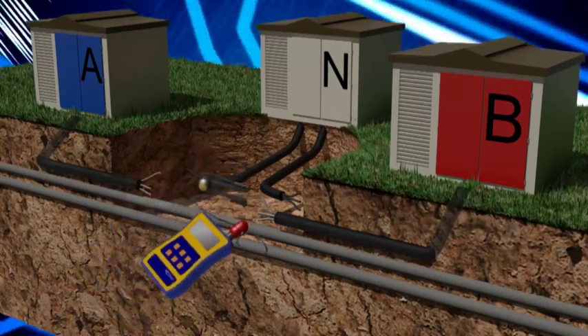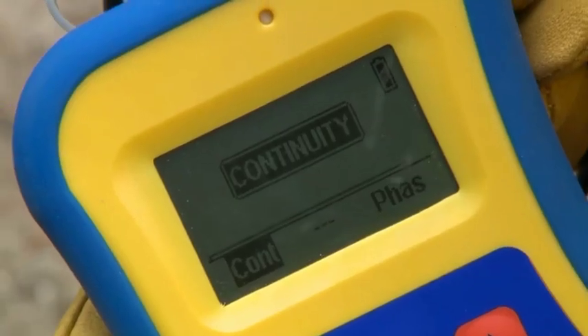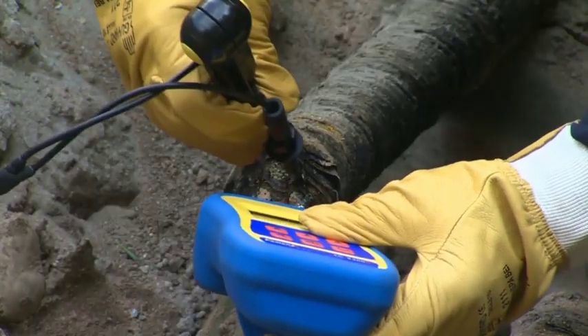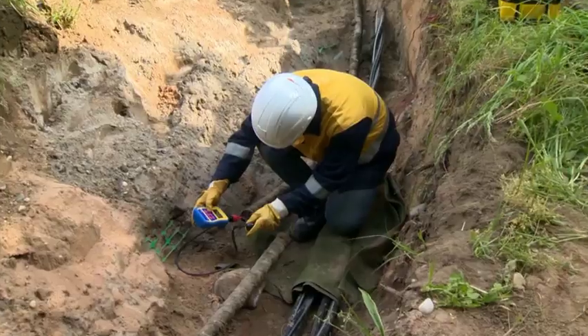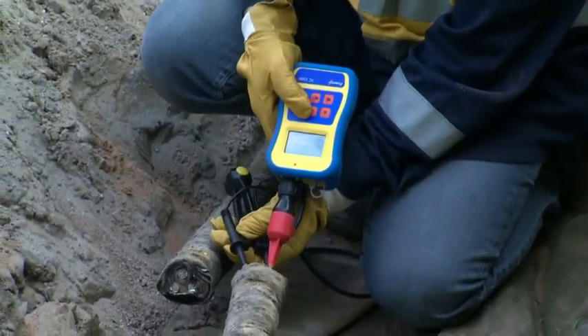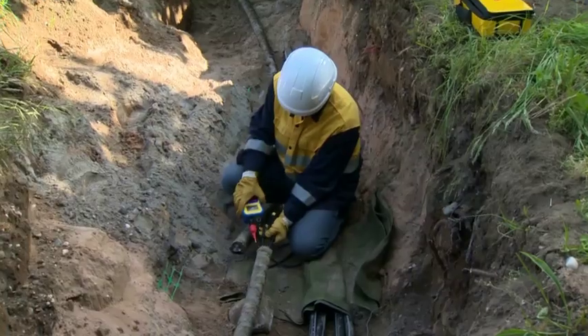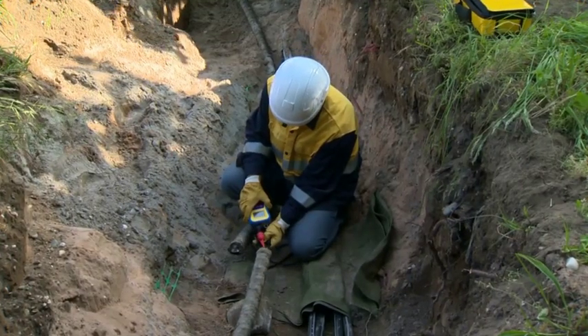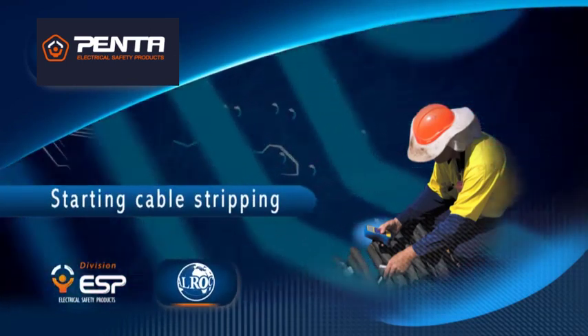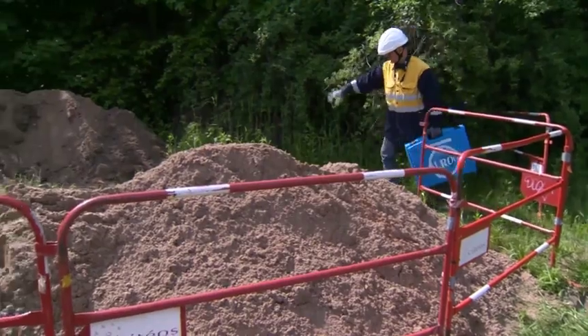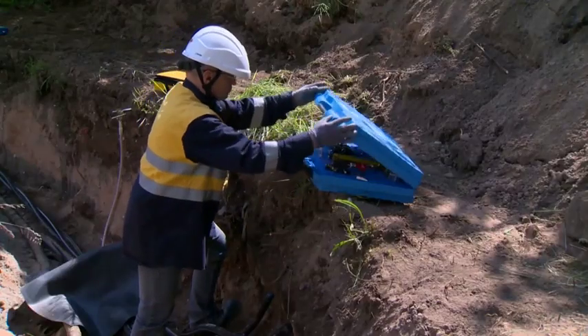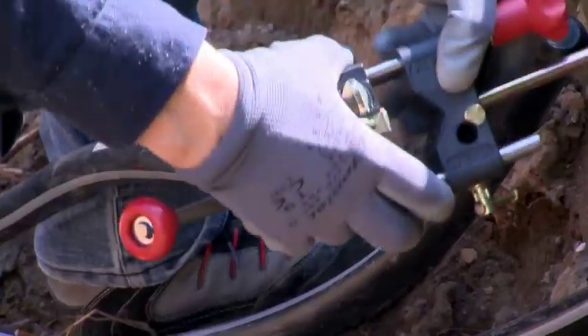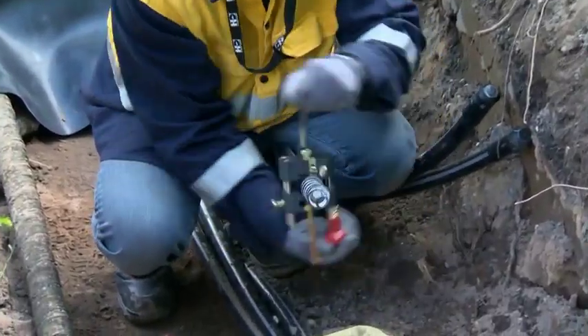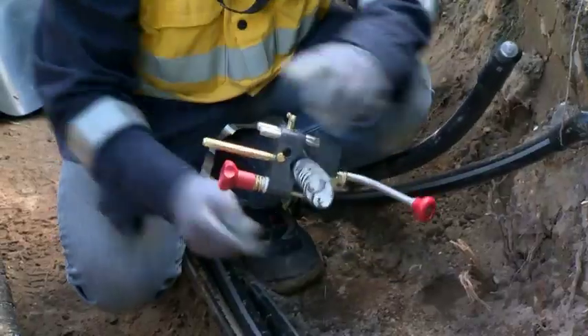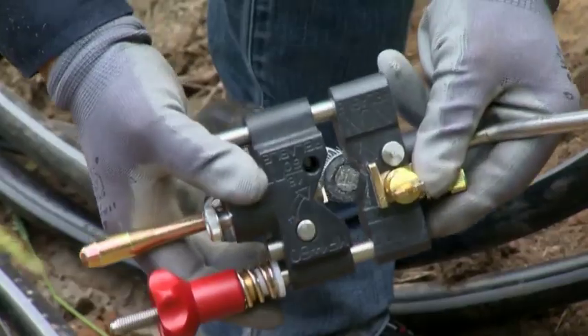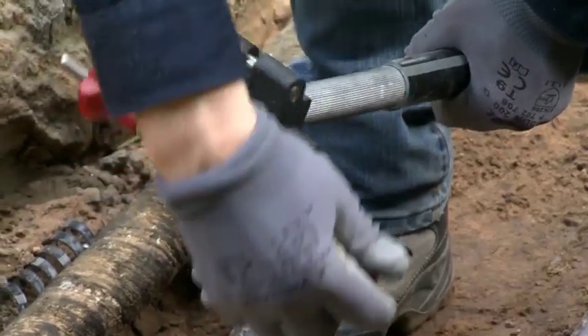There is still one more operation to ensure work is carried out on the disconnected cable. You must test for continuity, meaning reception of identification signals of all three phases from each transmitter. Now that we're certain of being protected by proper grounding of both ends of the cable, we can start preparing the cable ends to set up the connections. You save time by applying the right professional methods, using the right tools, so you don't have to come back in 6 months.